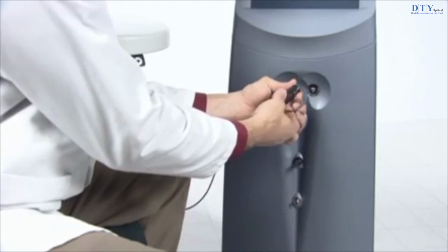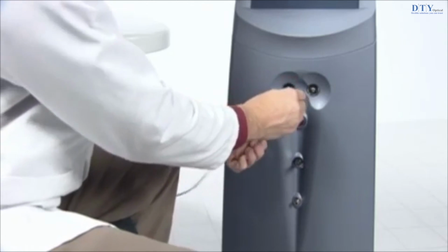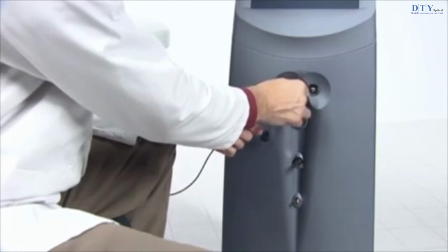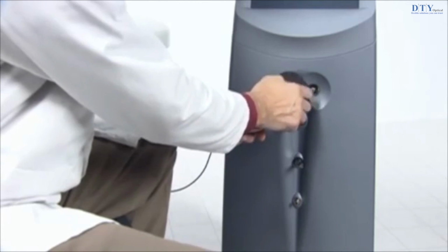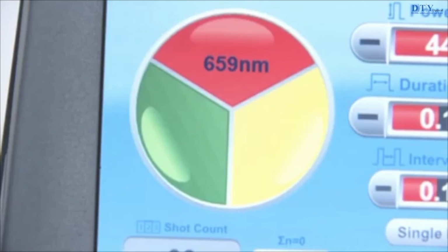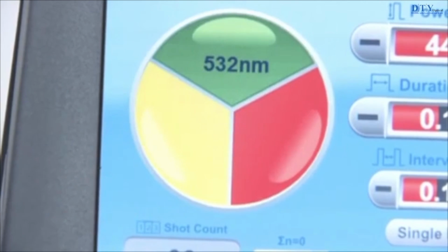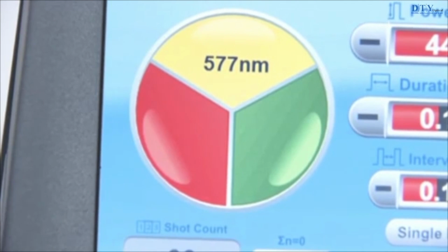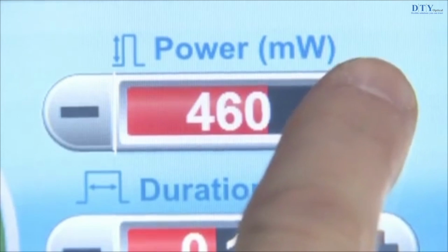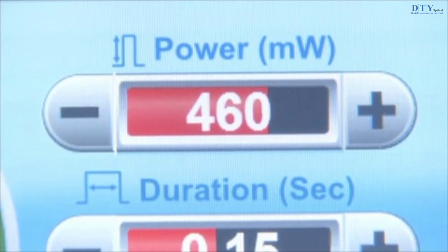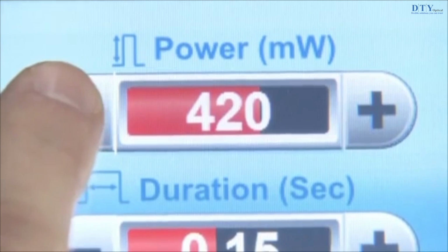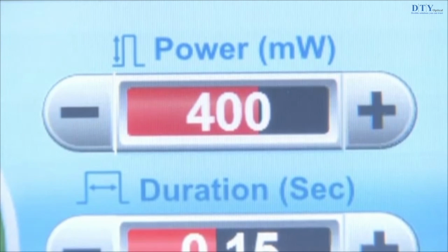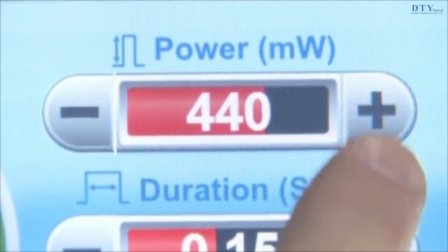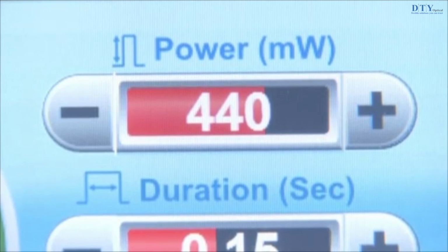If using a compatible laser indirect ophthalmoscope, you may also connect an LIO illumination power receptacle on the front of the laser console. The range of power settings varies for each laser color. See specifications in the Maintenance chapter of the Operator's Manual for the available settings for your laser. If you attempt to select a power setting that is not available for the current color, the laser emits a low-toned beep to indicate that you have reached the minimum or maximum available power.